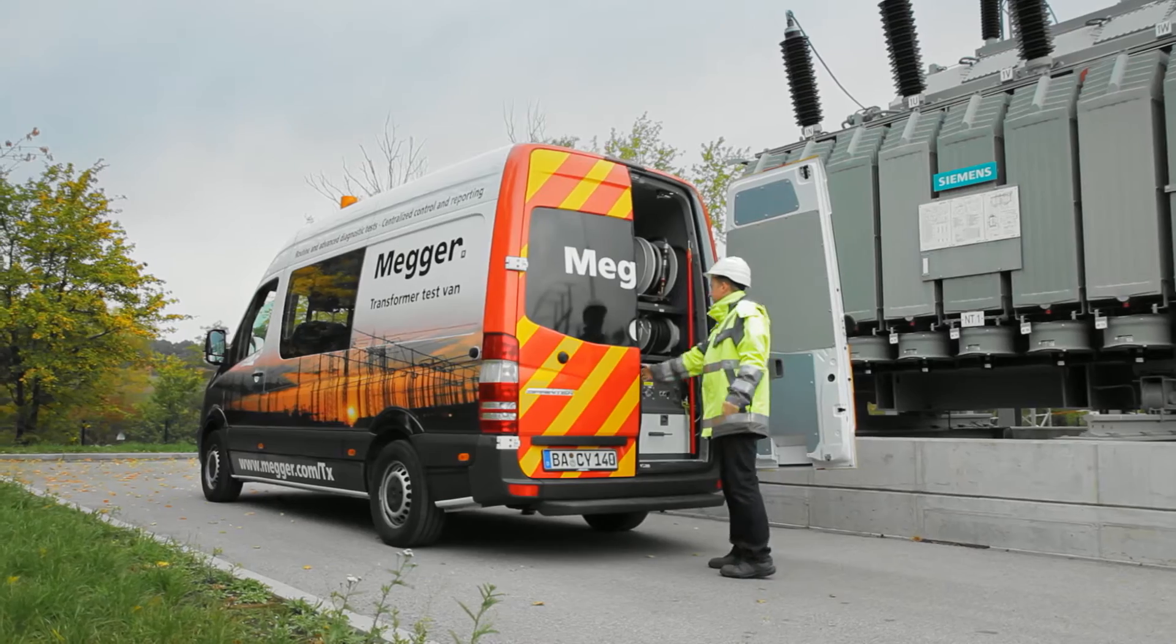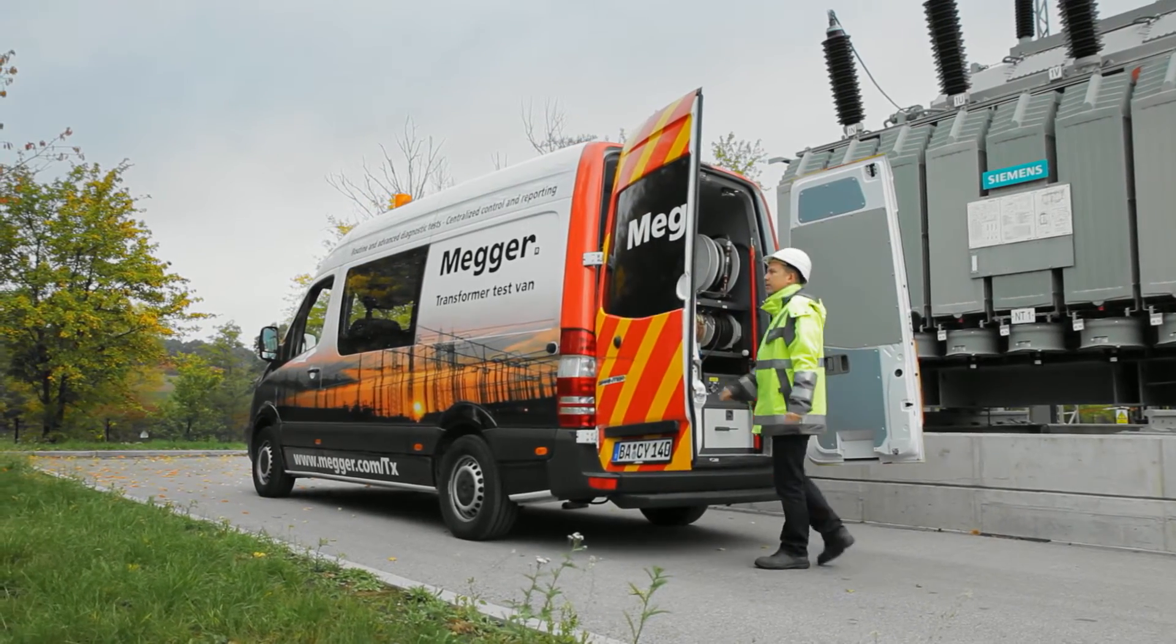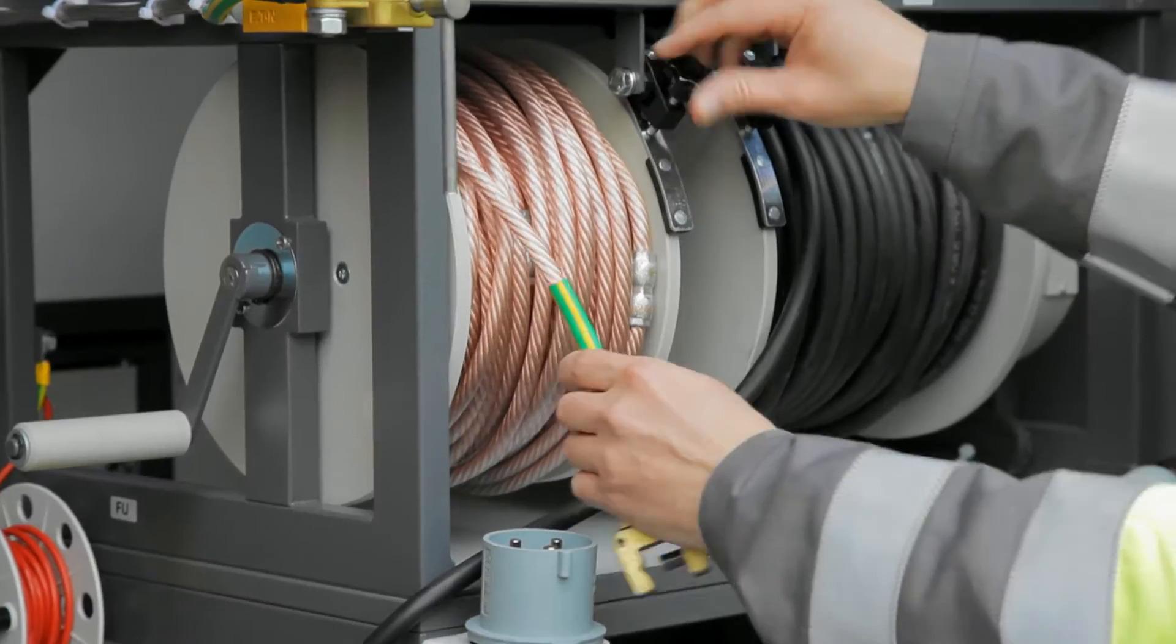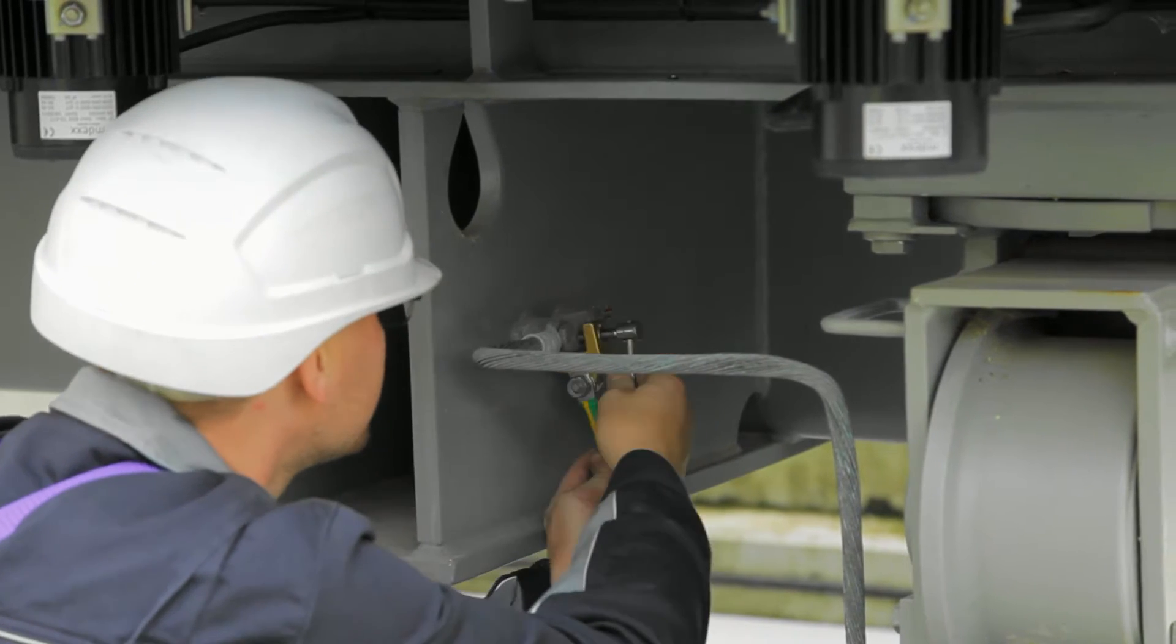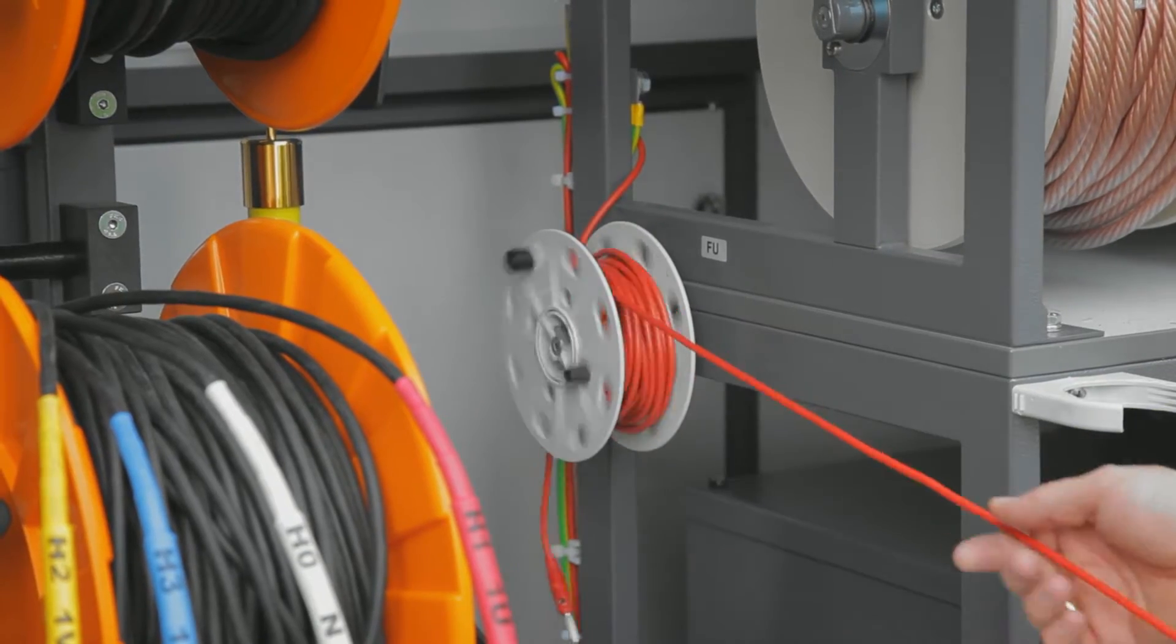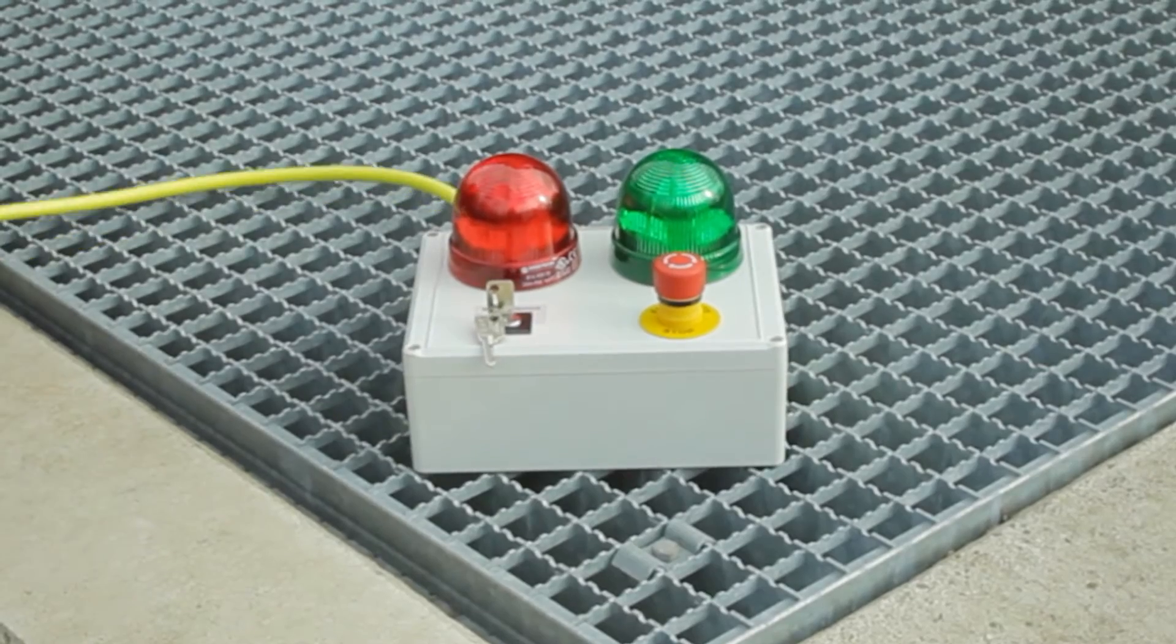The biggest advantage of the transformer test van solution compared to separate or multifunctional instruments is its immediate readiness to test. All leads are on reels pre-connected to the test instruments. Software-controlled switching eliminates manual reconfiguration, improving productivity, safety and user comfort, not to mention the air-conditioned office-like working environment of the van itself.